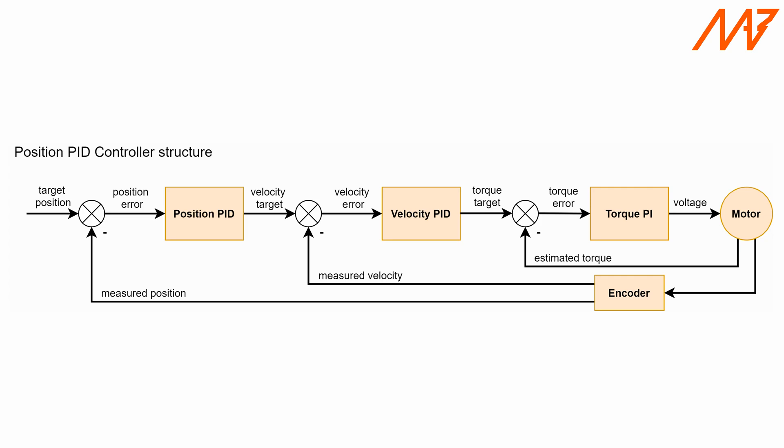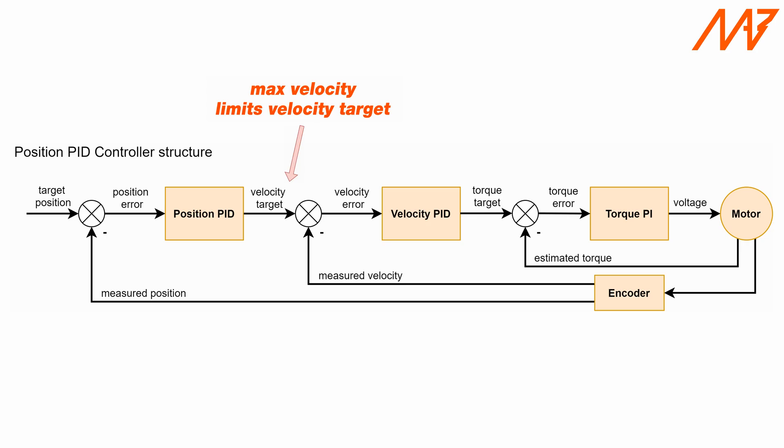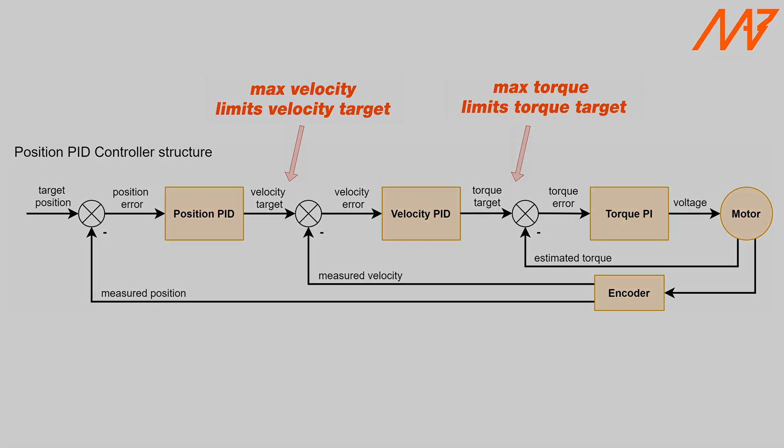For tuning purposes be sure to always tune the velocity controller first. During adjusting the gains to your needs you will find out that besides the PID controller gains there are two more parameters namely the max velocity and max torque. These parameters allow for limiting both controller outputs. With max velocity you can limit the velocity of the shaft between the respective position points and with max torque the maximum torque that can be applied to reach that position.